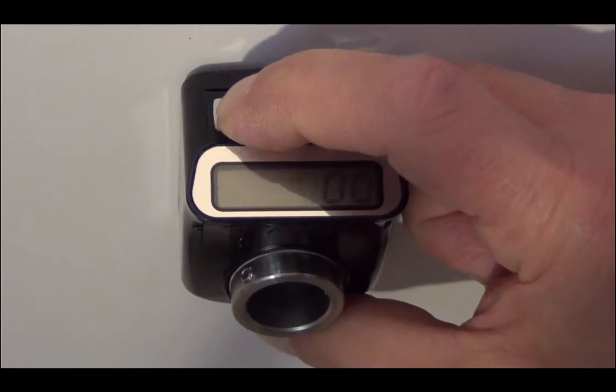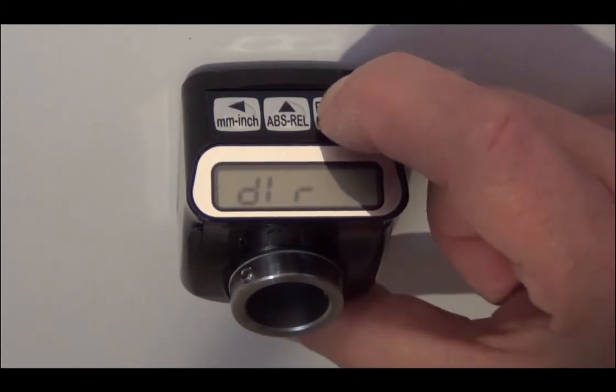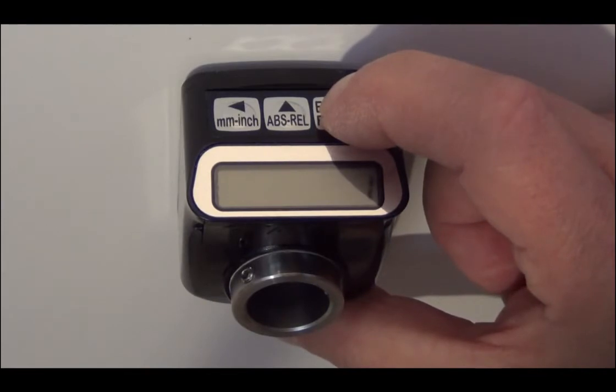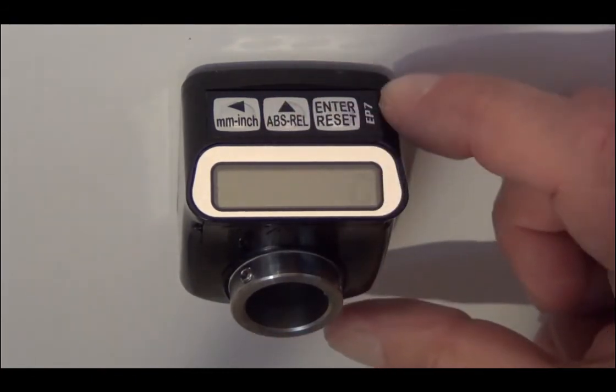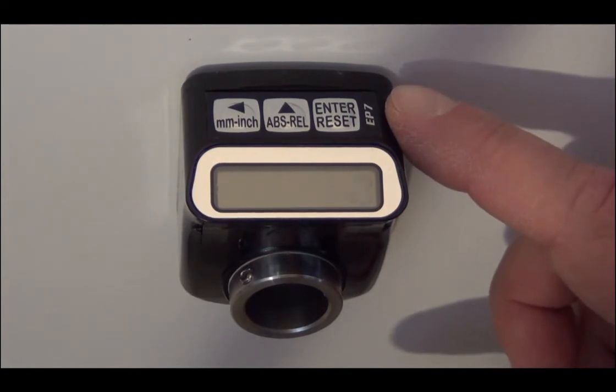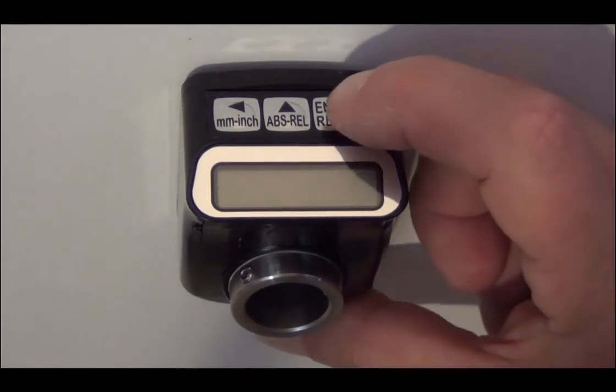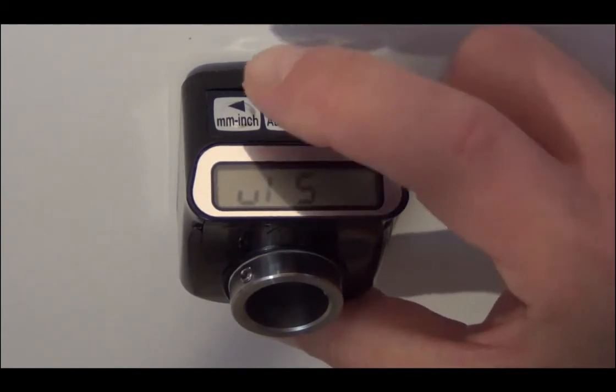DIR, or counting direction, will now be displayed. Depress ENTER twice. Once to initiate the programming mode, the second activates the least significant digit of the direction entry. Use the COUNT UP button to select either 0 or 1, 0 for clockwise-increasing count direction, and 1 for counter-clockwise-increasing count direction. Depress ENTER when complete.